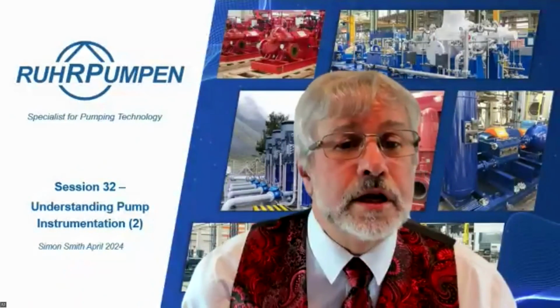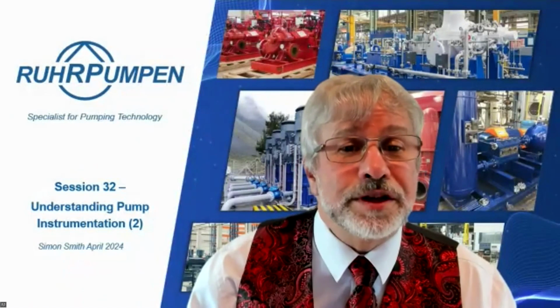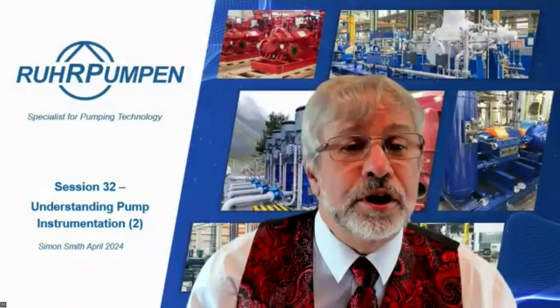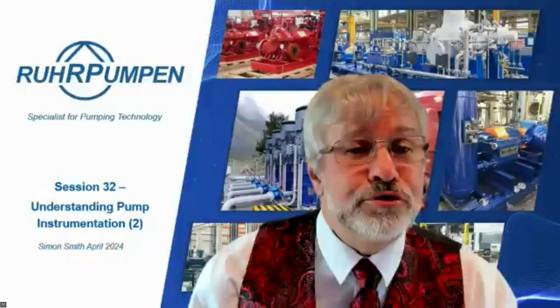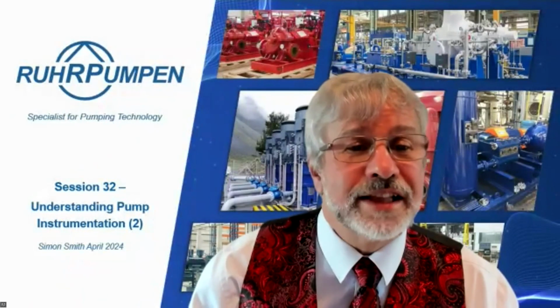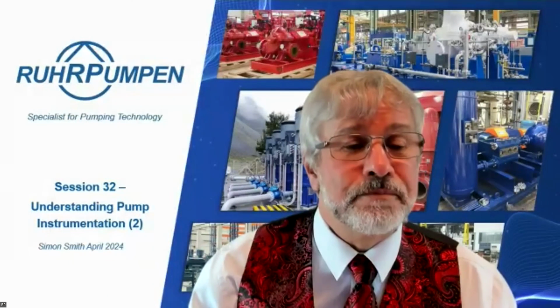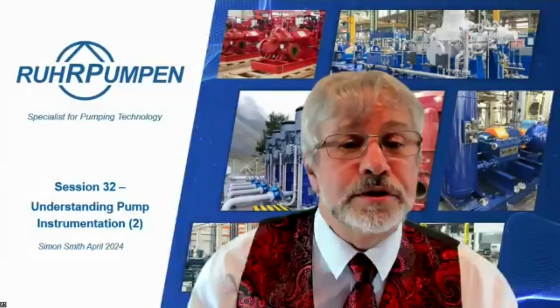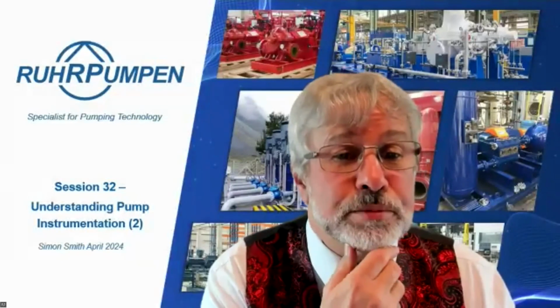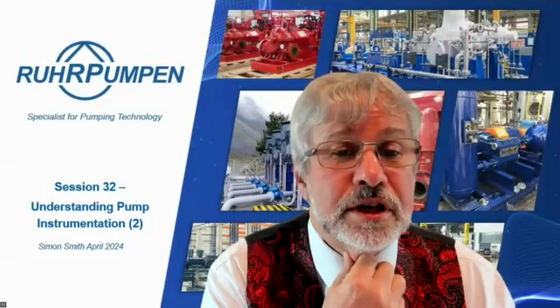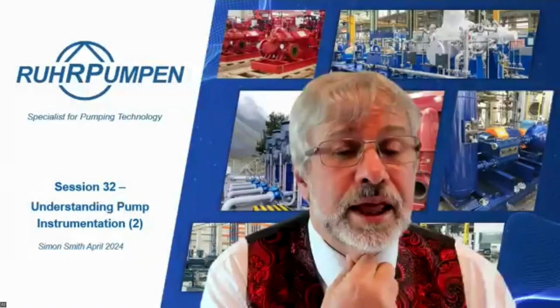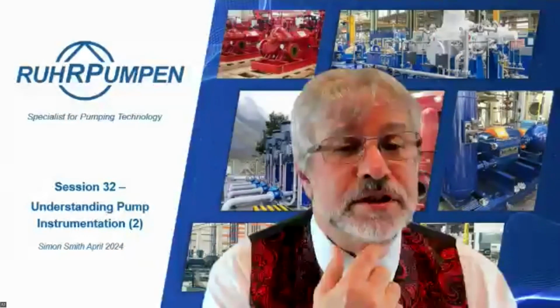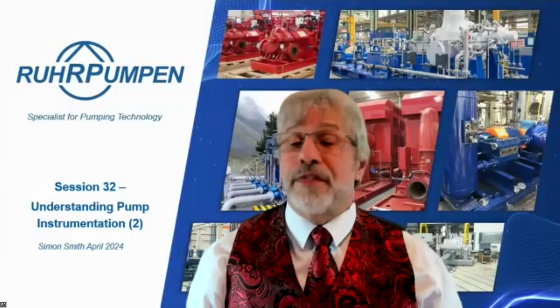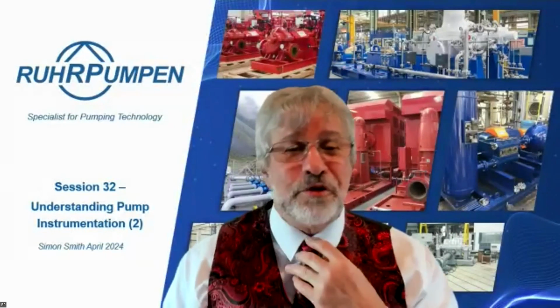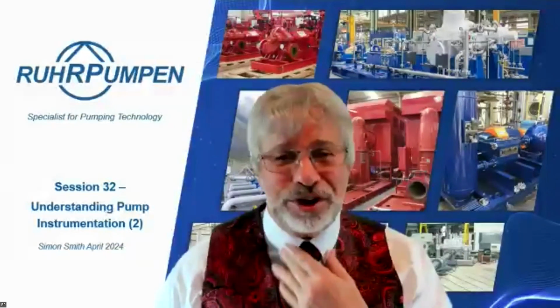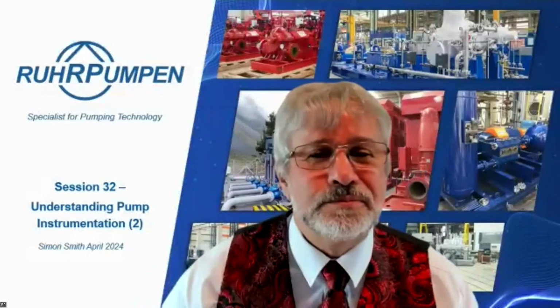Hans Bert says, answer to one of your first Q&A questions, RTDs are more accurate compared to thermocouples, but have a limited range. Thermocouples can handle higher temperature ranges and react faster. Thermocouples are typically used, for example, in mag drive temperature monitoring. For bearing temperatures, speed is not that critical. Hence, RTD most of the time is sufficient if the temperatures are not elevated. Thank you, Hans. That confirms what I said in a lot more detail. So thank you very much for that.